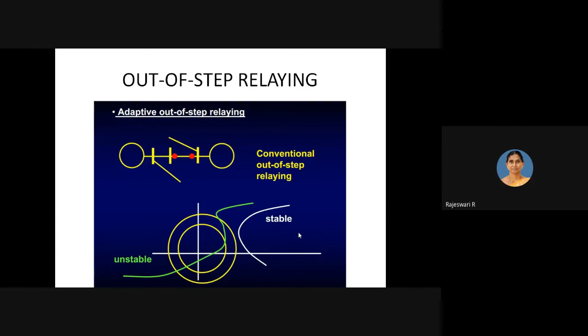That is possible with synchrophasor technology, by accessing the synchrophasor measurements. If the decision is made by out of step relaying using them, then it is possible to distinguish the stable and unstable power swings, which may happen due to a large loss of load or shutting down of generators. Major disturbances may cause such power swings. So out of step relaying should be able to distinguish a fault from a power swing, and stable from unstable swing. This is possible only when it has access to phasor measurements.